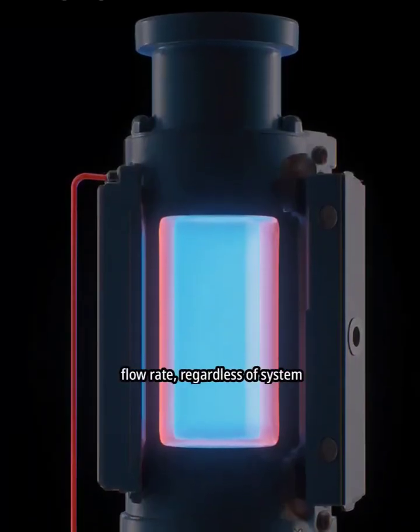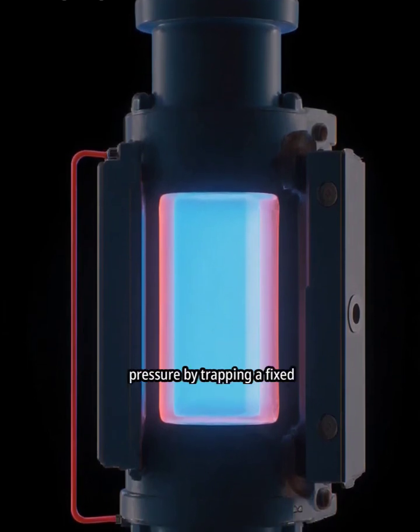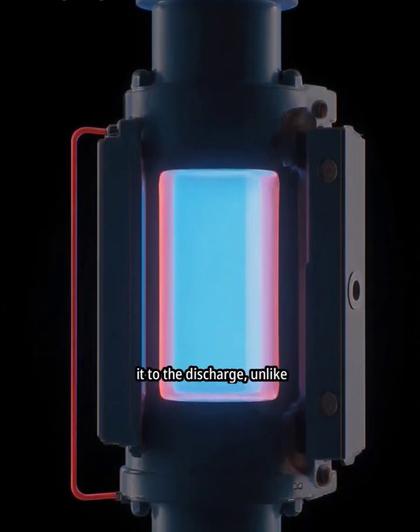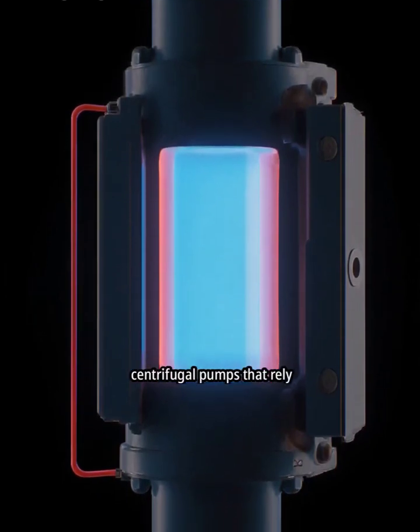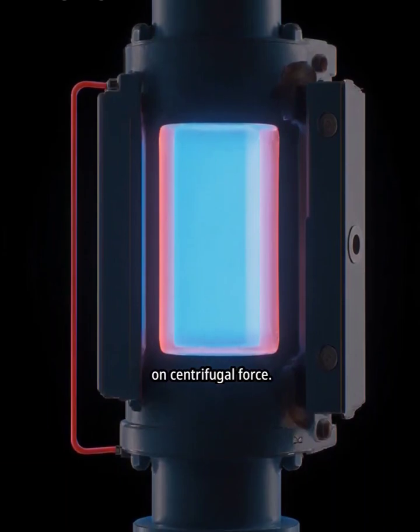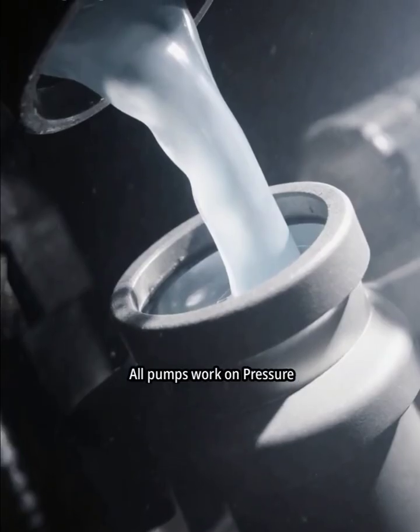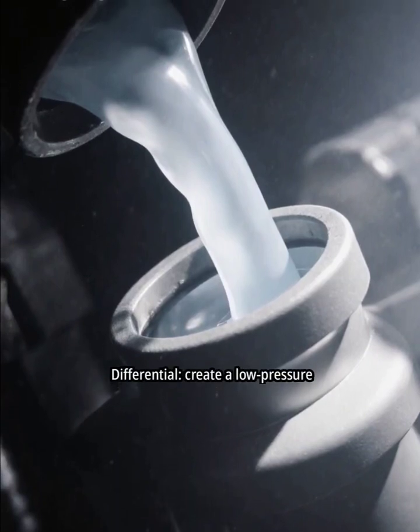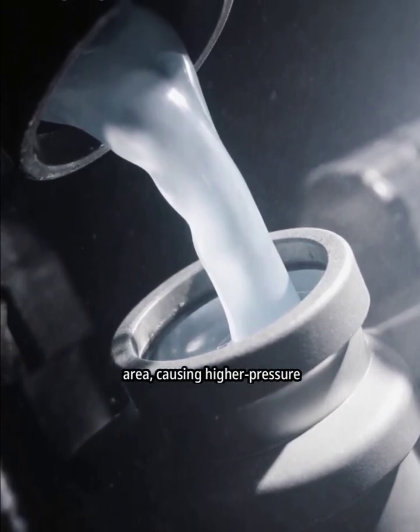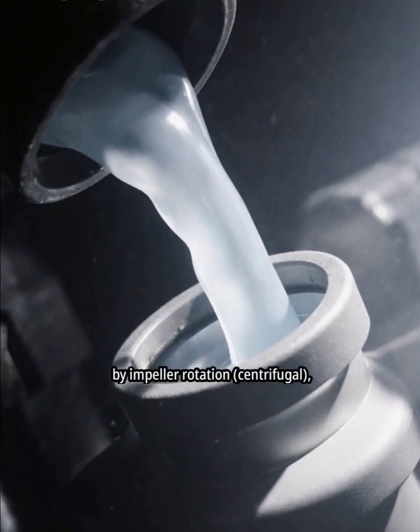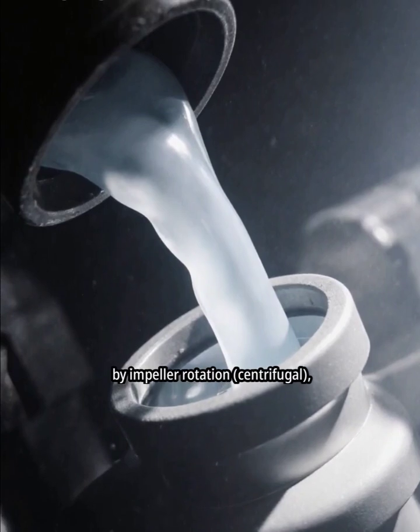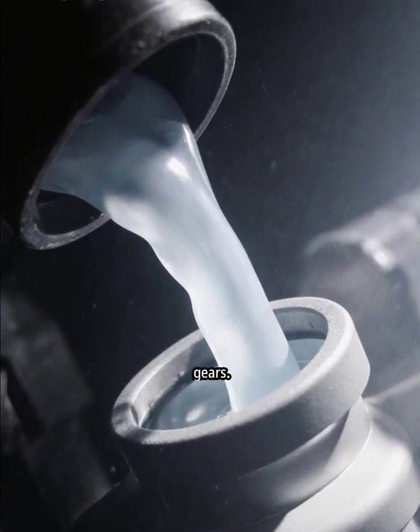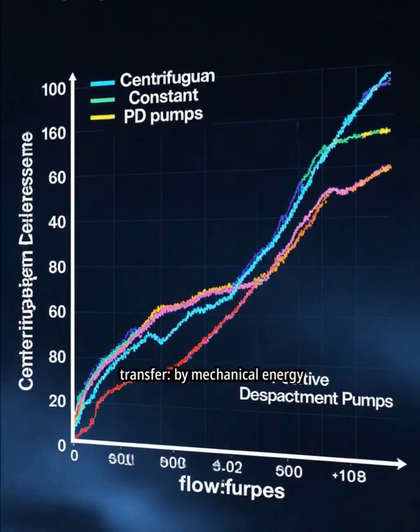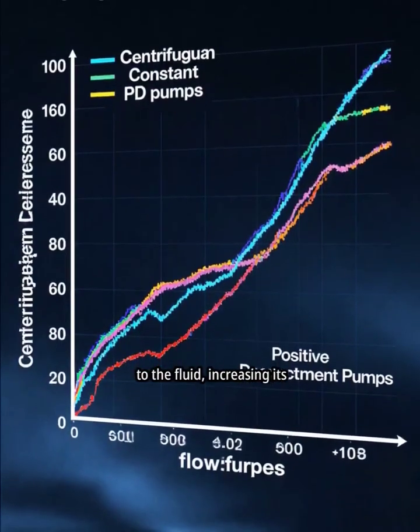A PD pump provides a constant flow rate, regardless of system pressure, by trapping a fixed amount of fluid and forcing it to the discharge. Unlike centrifugal pumps that rely on centrifugal force, all pumps work on pressure differential. They create a low pressure area, causing higher pressure fluid to flow in, whether by impeller rotation (centrifugal), piston movement, or meshing gears. In pumps, there is energy transfer by mechanical energy to the fluid, increasing its pressure and potential energy.